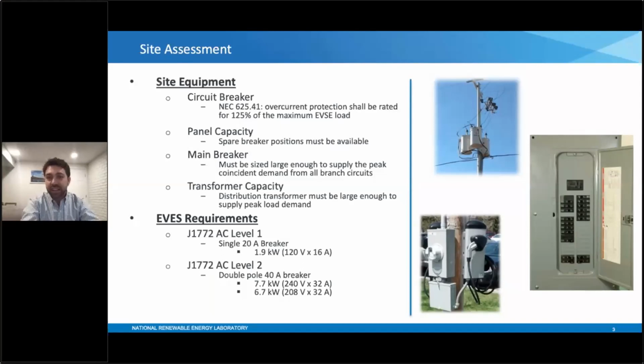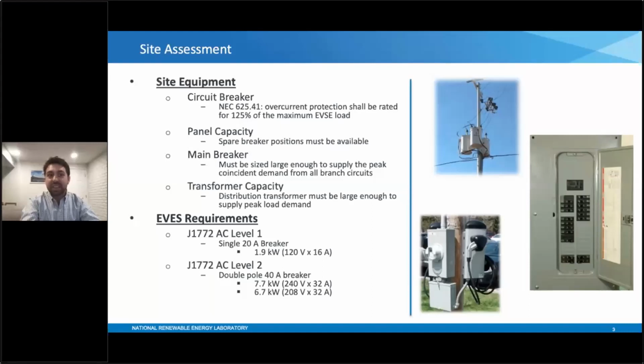Contrary to that, the level 2 standard actually is open to a couple different types of service options. Most common with residential homes, you have 120 volt or 240 volt services. 240 volt is most commonly associated with your air conditioning units, sometimes your dryer units, and it's those more sophisticated sockets that actually have 4 prongs typically instead of just 3. And that 240 volt service actually requires a double pole breaker because you're pulling in 2 legs of that 120 volt service there. And they're commonly for 240 volt 7.7 kilowatt units, which means that they require about 32 amps. So that 32 amps, again, if you make sure you have that NEC breaker protection there with the overcurrent buffer of 125%, that gets you to about a 40 amp rating on the breaker. And that's where you need actually a double pole breaker to protect 40 amps for these units.